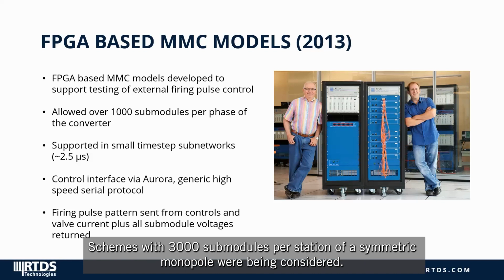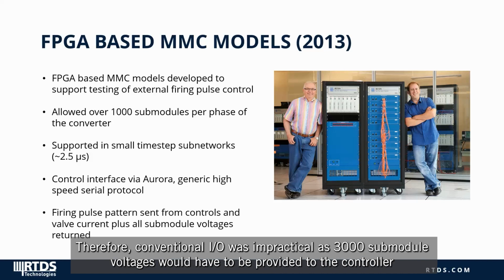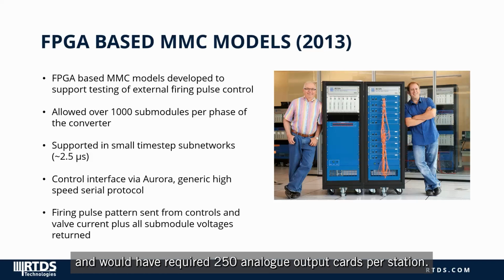Schemes with 3,000 submodules per station of a symmetric monopole were being considered. Therefore, conventional I/O was impractical, as 3,000 submodule voltages would have to be provided to the controller and would have required 250 analog output cards per station.